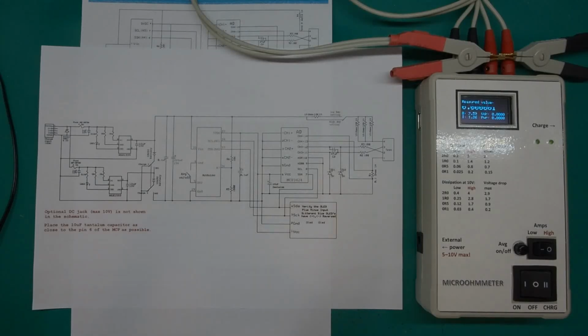Sometimes a current of more than 1 amp is too much to handle for the device under test, so the measuring current can be switched from approximately 1.2 amps to 300 milliamps. That depends on the load also. Keep in mind that 300 milliamps will not be enough for a true 1 micro-ohm resolution measurement, so this has to be taken into account.